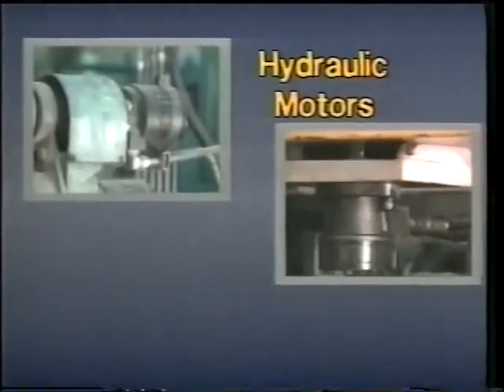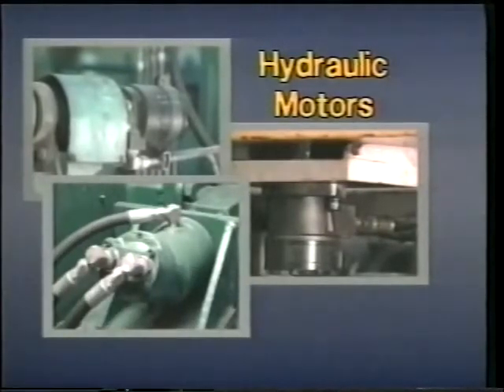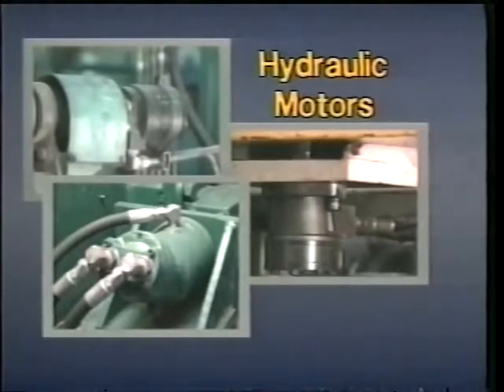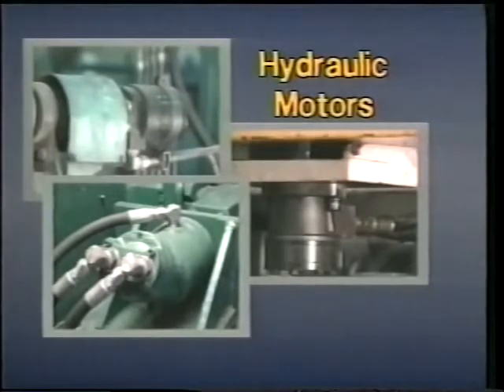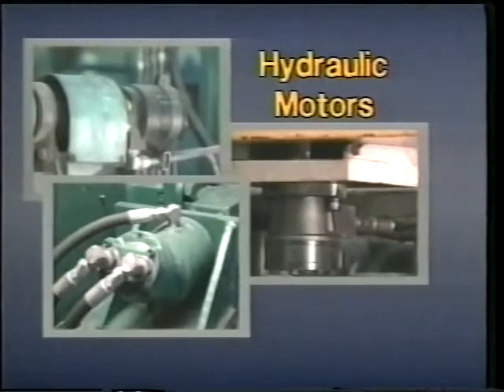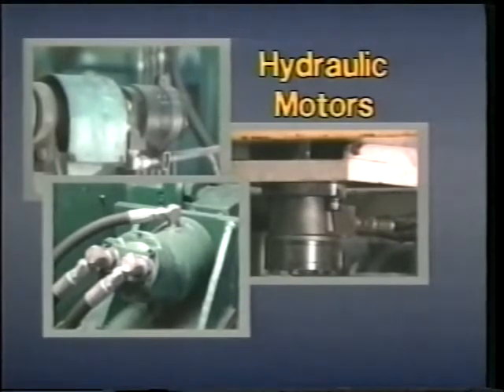Three types of motors are commonly used in industrial hydraulic systems: the vane motor, the gear motor, and the piston motor. While each of these motors looks similar to its counterpart pump, each operates on a principle exactly opposite of the pump. Hydraulic motors take fluid under pressure, apply it to the surface area of an internal moving part to create a rotary force, and then return the fluid to tank.